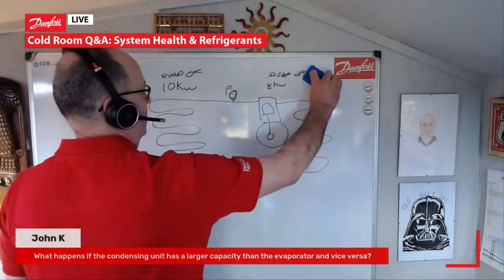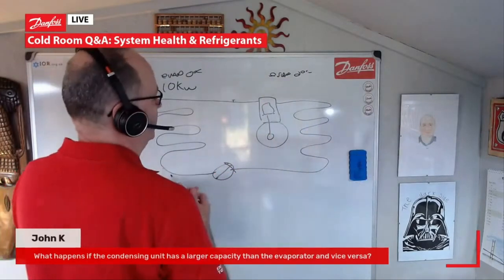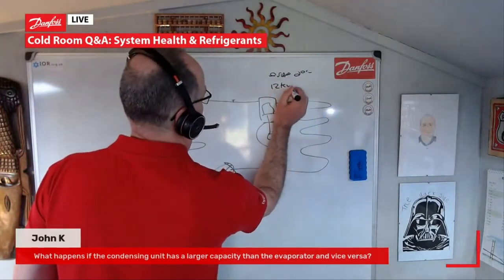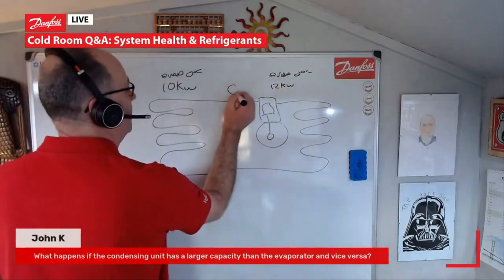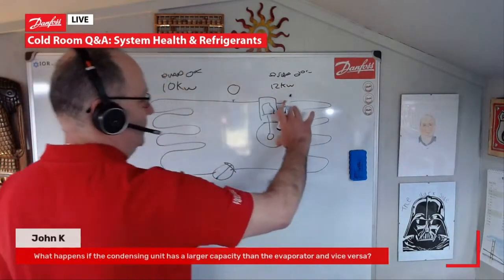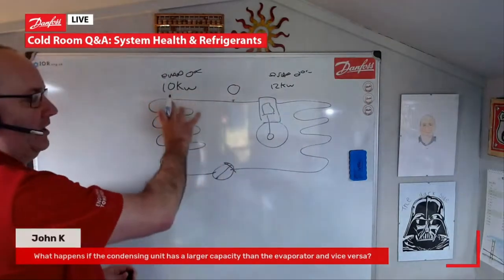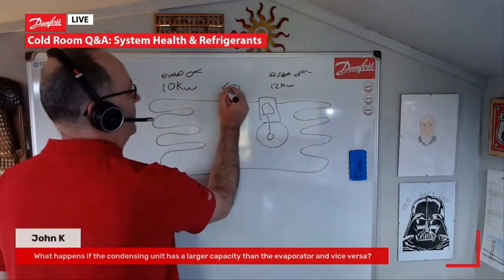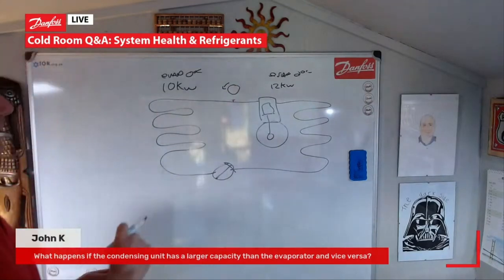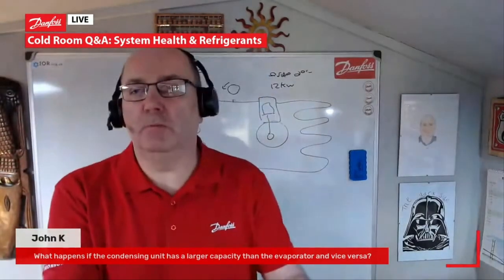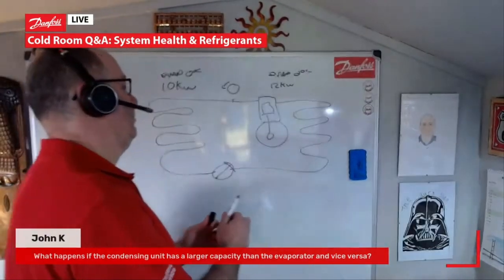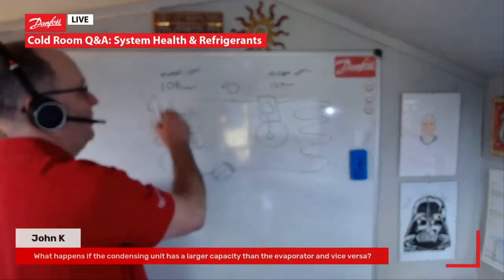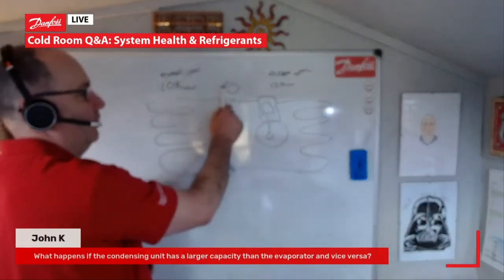If we then change things around and say we've got a 12 kilowatt compressor, that now can do more duty than our evaporator can actually provide. So our suction pressure is going to fall a little bit. You can work this out on balance graphs and balance tables — most of it's done nowadays on selection software for the evaporators. But in essence, if you've got a larger compressor than the evaporator, your suction pressure will fall a little bit.